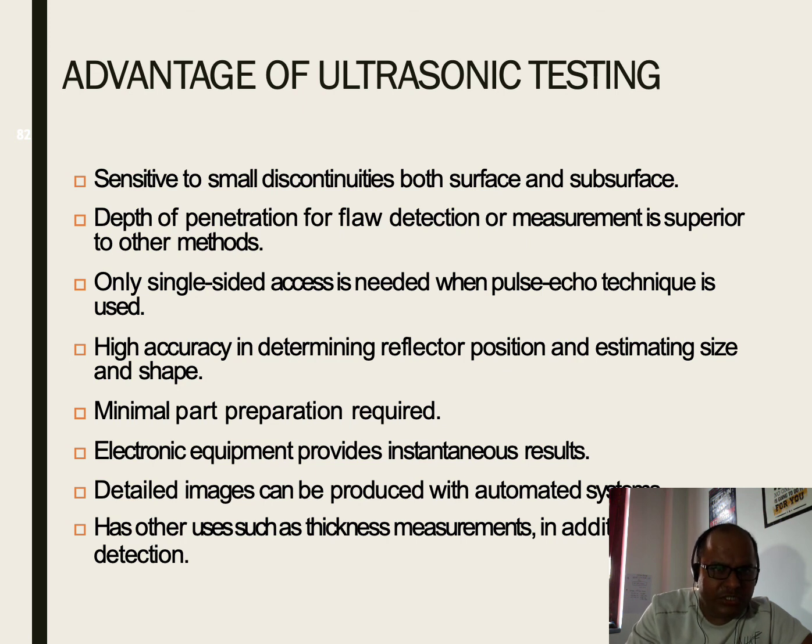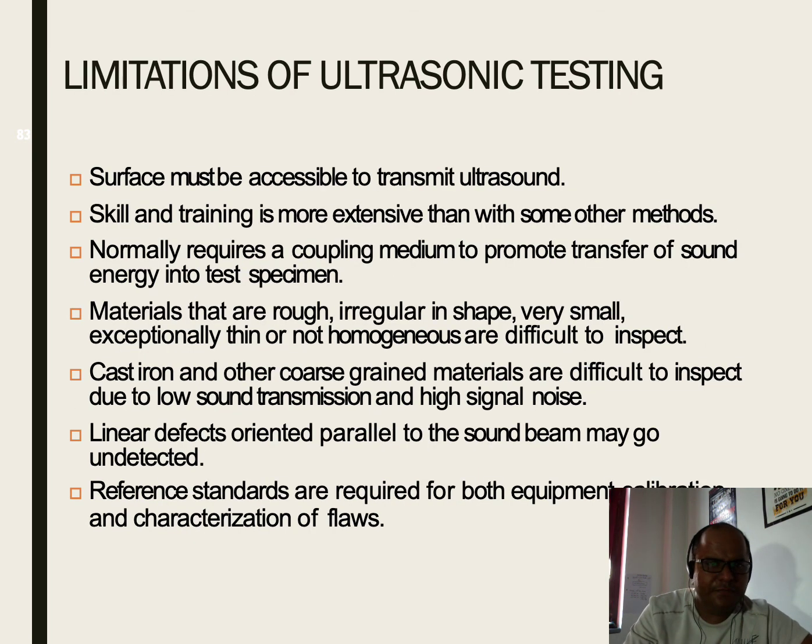High accuracy in determining reflector position and estimating size and shape. Minimal part preparation is required. Electronic equipment provides instantaneous results. Detailed images can be produced with automated systems, and it can be used for thickness measurement in addition to flaw detection. Limitations of ultrasonic testing.